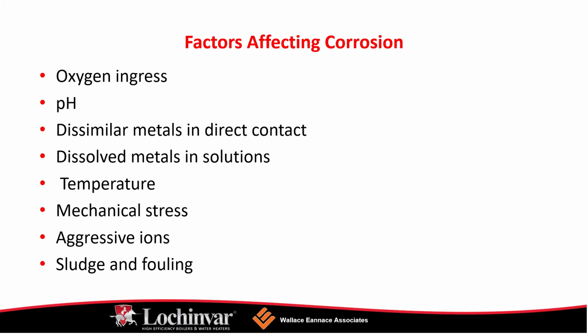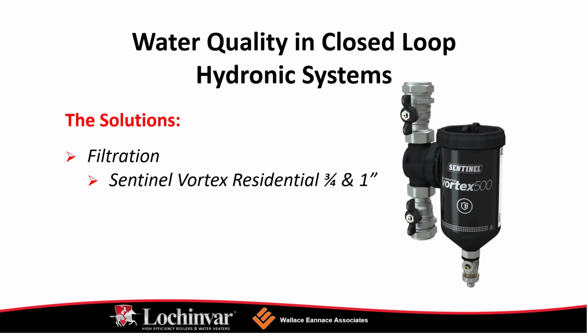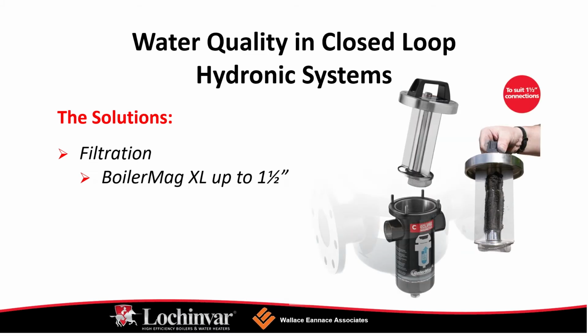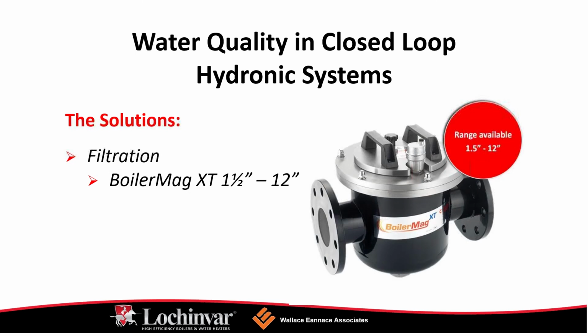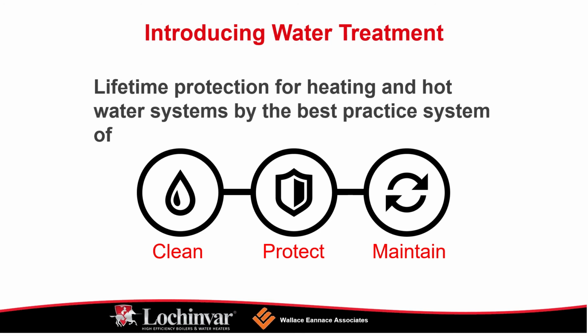Same holds true with the circulator, not your father's circulator. So ECM pumps, which are now compulsory, are part of rules and regulations now and enforced, especially as of 2020. And they have a very low tolerance for magnetite, so we have to be able to compete against that. Other factors affecting corrosion: oxygen ingress, pH, dissimilar metals in direct contact with one another, dissolved metals in solutions, temperature, mechanical stress, aggressive ions, sludge, and fouling.